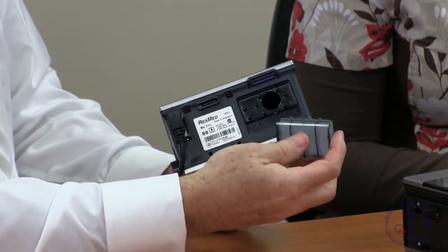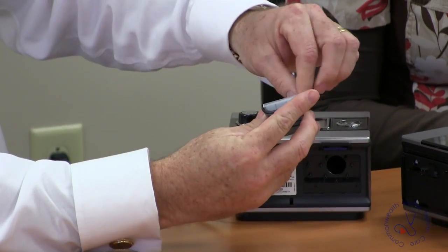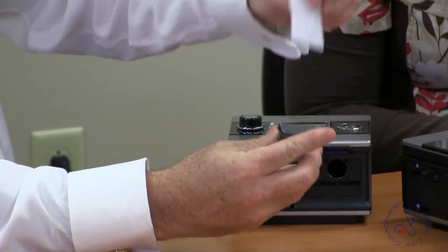The other thing on the back of the machine is a filter. You've got a filter here that comes apart, that basically is thrown away, and we put a new filter into the device. You can tell by discoloration when it changes color, and you can actually see the dirt. When you open it and look at it, typically once a month would be the most frequent, but some people are funny too. They'll open it up, see the dirt and want to put a new filter in. But your insurance company typically, from a reimbursement perspective, will let you get a new filter for your device once a month. And it just plugs right there on the back. It's very simple to get to.